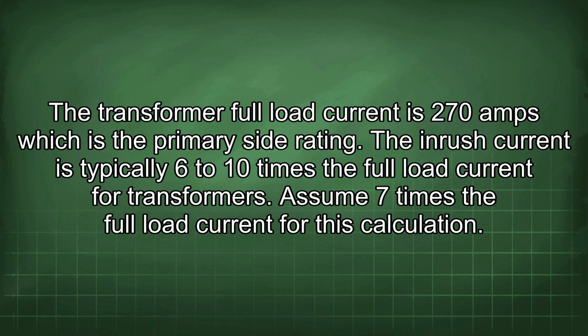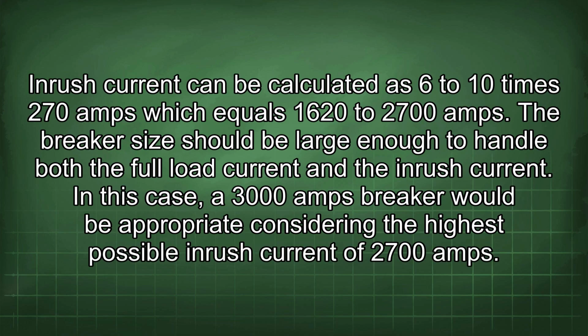The inrush current is typically 6 to 10 times the full load current for transformers. Assume 7 times the full load current for this calculation. Inrush current can be calculated as 6 to 10 times 270 amps, which equals 1620 to 2700 amps. The breaker size should be large enough to handle both the full load current and the inrush current. In this case, a 3000 amp breaker would be appropriate considering the highest possible inrush current of 2700 amps.